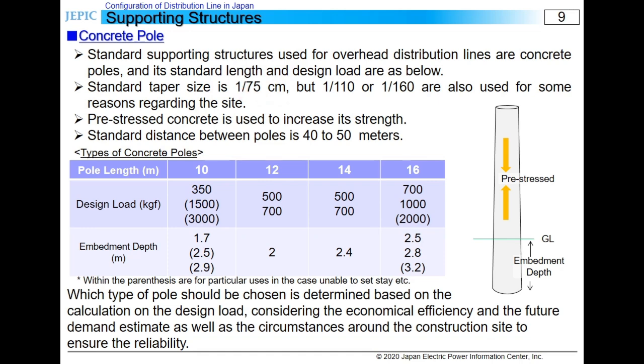For the purpose of avoiding being a disturbance to traffic or the site, thinner types like the 1/110 centimeter or 1/160 centimeter type are sometimes used. The numbers in parentheses are strain type poles, reluctantly used when a stay wire can't be put in for site reasons. These concrete poles are pre-stressed concrete poles whose reinforcing steel inside is tensioned during manufacturing so that the pole becomes stronger against cracks.